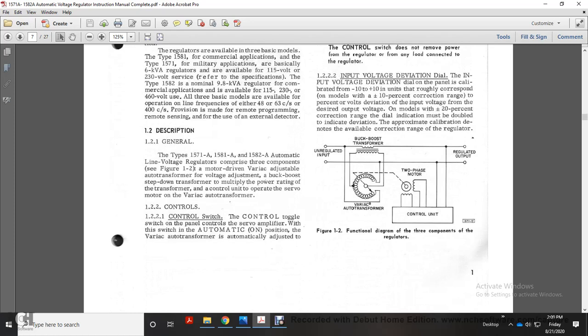automatic line voltage regulator comprises three components. See figure 1-2. The motor-driven Variac adjustable transformer for voltage adjustment, the buck-boost step-down transformer to multiply the power rating of the transformer, and the control unit operating as a servo motor with the Variac autotransformer.